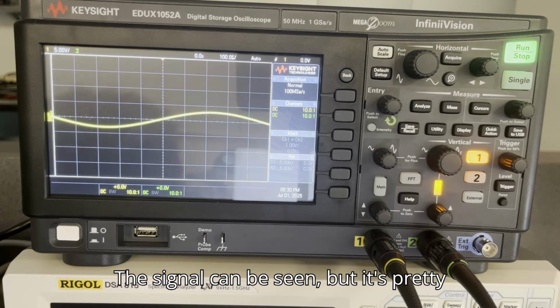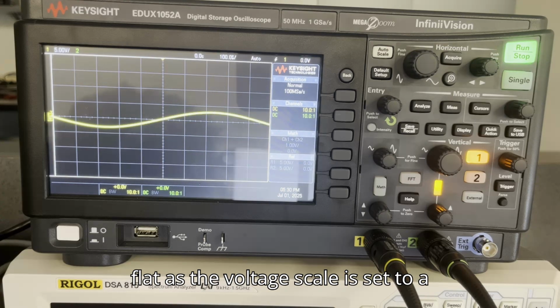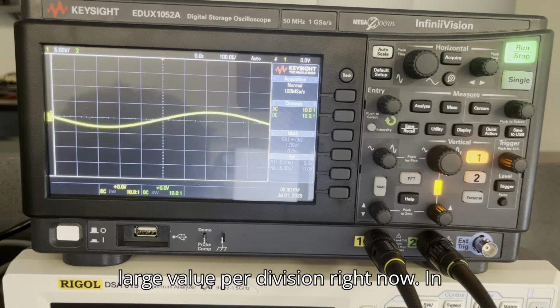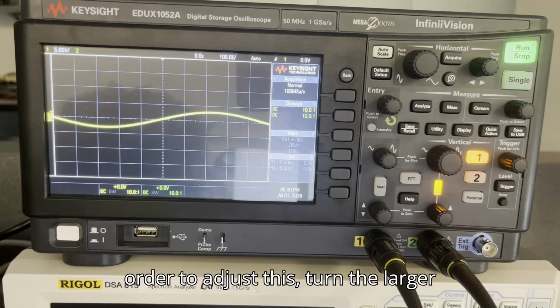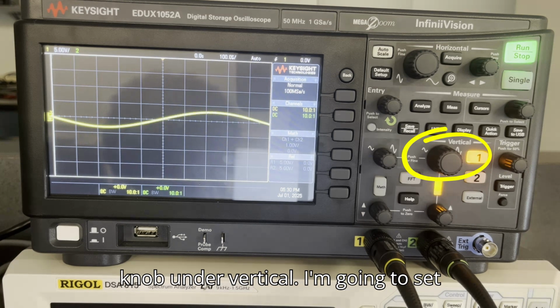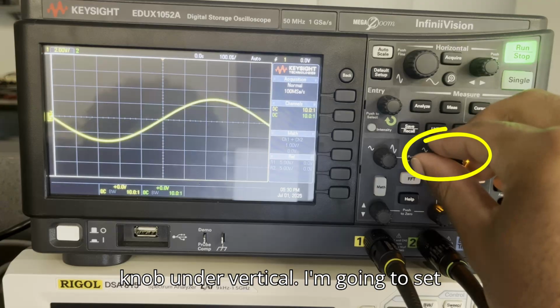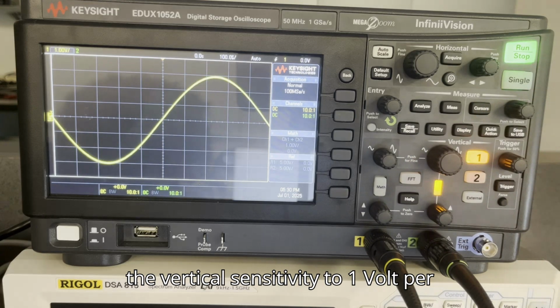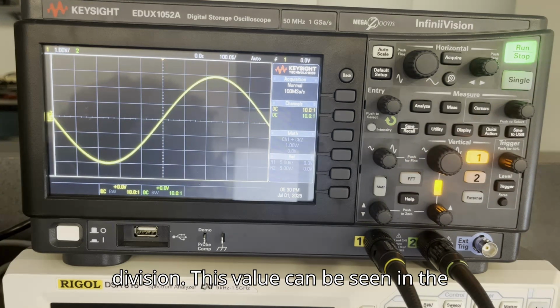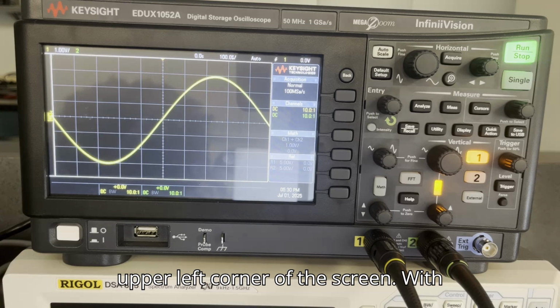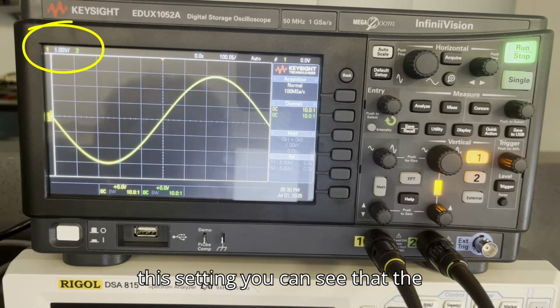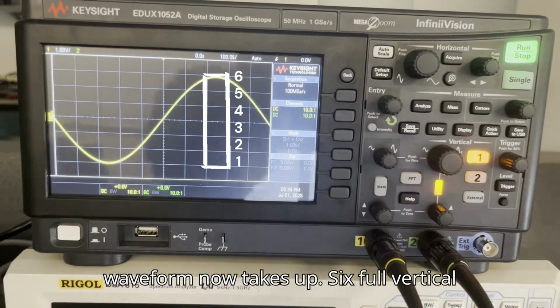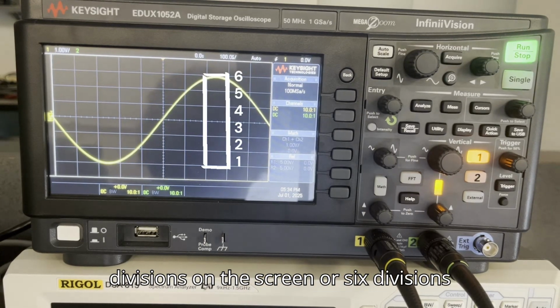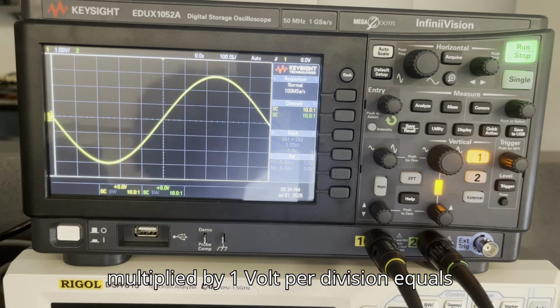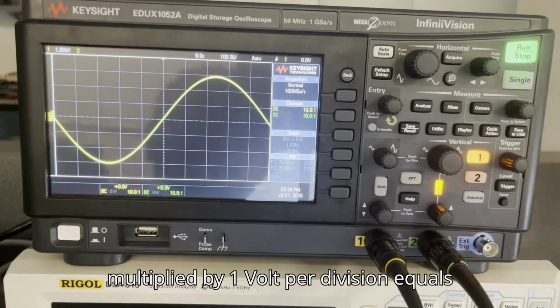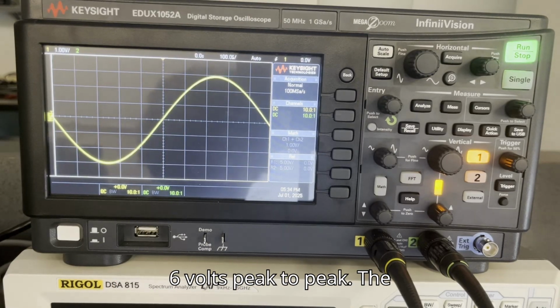The signal can be seen, but it's pretty flat as the voltage scale is set to a large value per division right now. In order to adjust this, turn the larger knob under vertical. I'm going to set the vertical sensitivity to 1 volt per division. This value can be seen in the upper left corner of the screen. With this setting, you can see that the waveform now takes up 6 full vertical divisions on the screen, or 6 divisions multiplied by 1 volt per division equals 6 volts peak to peak.